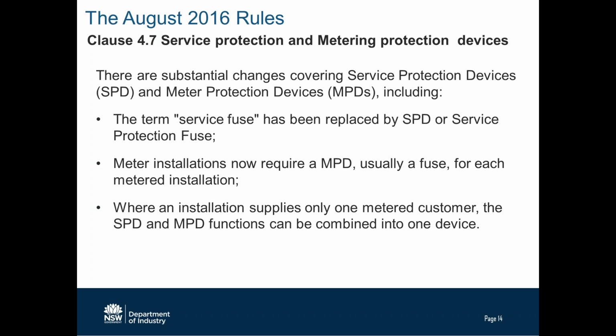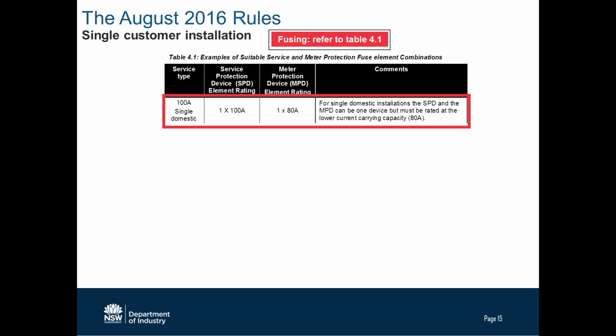on each metered customer. Where you've got a typical domestic installation with only one metered customer, the service protection device and meter protection device can be combined in one. So basically the old service fuse can now become a combined SPD and MPD, but it must be an 80 amp rated fuse in there. Still requiring a 100 amp fuse base, just to make sure we don't get any heating problems, and because they're readily available anyway. But the cartridge in those devices must now be an 80 amp fuse, and this is clarified. So that's the rule in there.